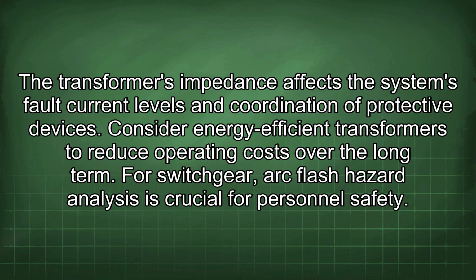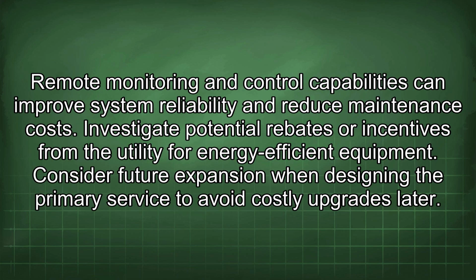The transformer's impedance affects the system's fault current levels and coordination of protective devices. Consider energy-efficient transformers to reduce operating costs over the long term. For switchgear, arc flash hazard analysis is crucial for personnel safety. Remote monitoring and control capabilities can improve system reliability and reduce maintenance costs.